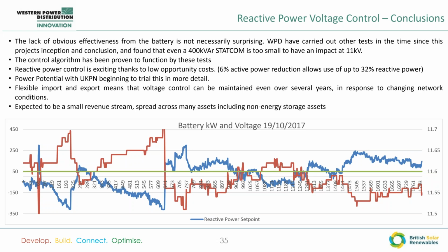Positives to take from this use case is that the control algorithm worked flawlessly. It gave proportional responses to changes in voltage, which I've demonstrated with that graph below there. You can see that there's mirror lines either side of that 11.6 kV volt line there in green.